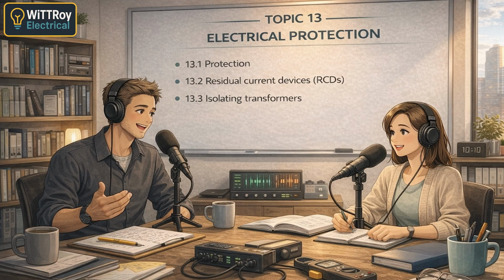It does not operate within 4 hours at 1.5 times current. So it allows more heating. Exactly. That's why it's considered less protective. Which devices use coarse protection? Mainly rewirable fuses. Those old fuse wires.